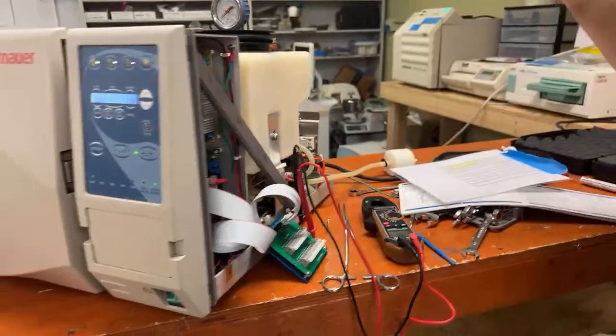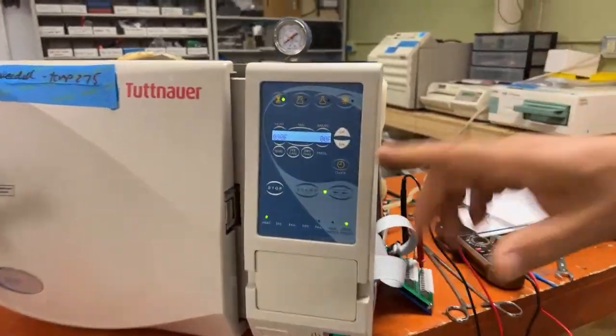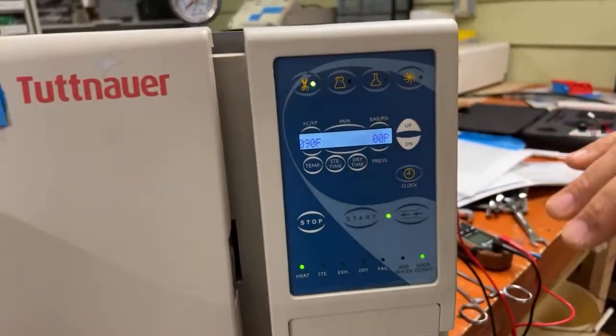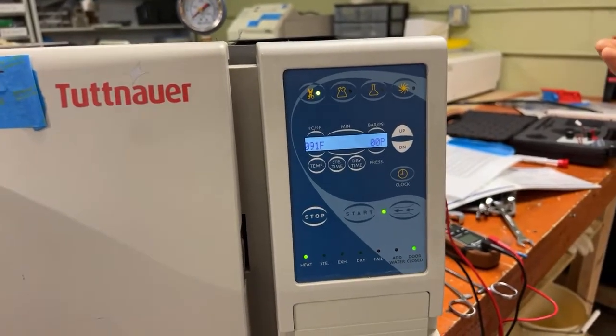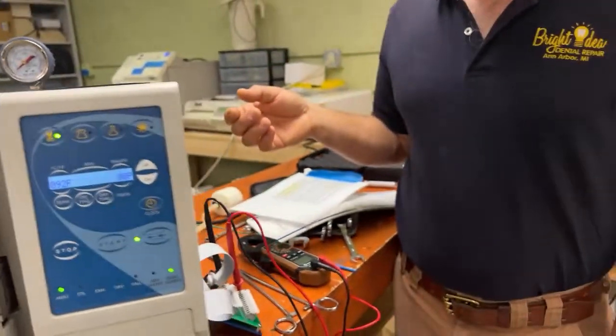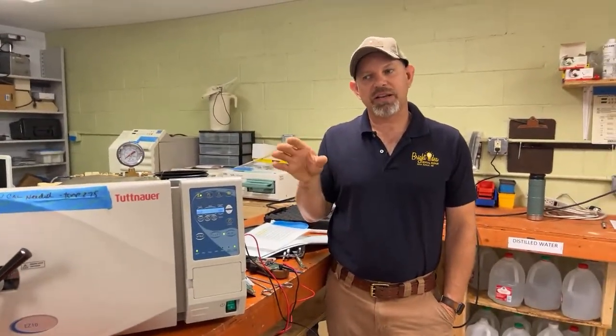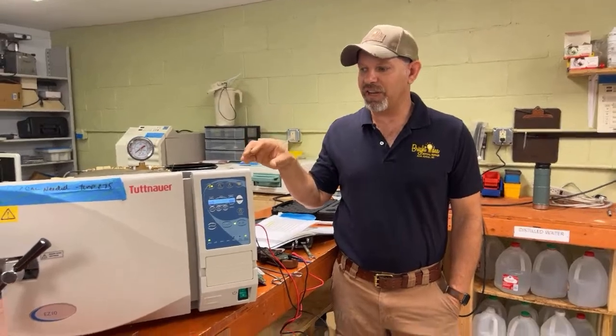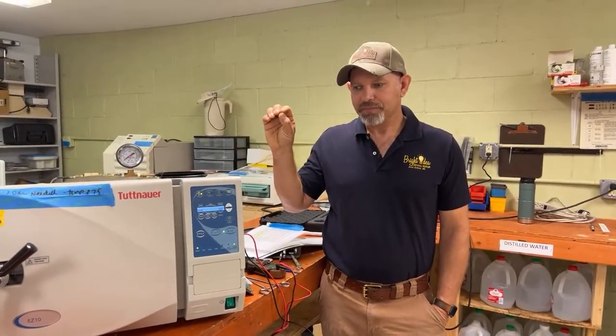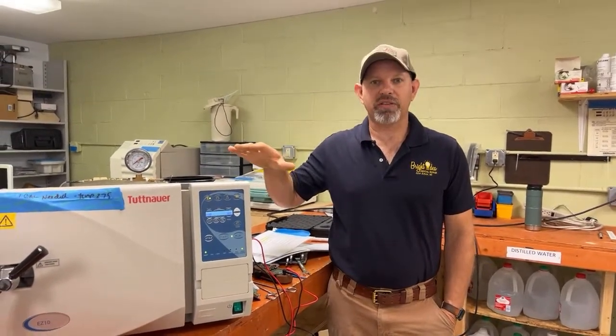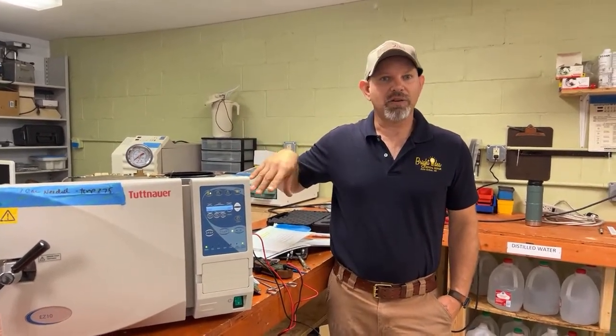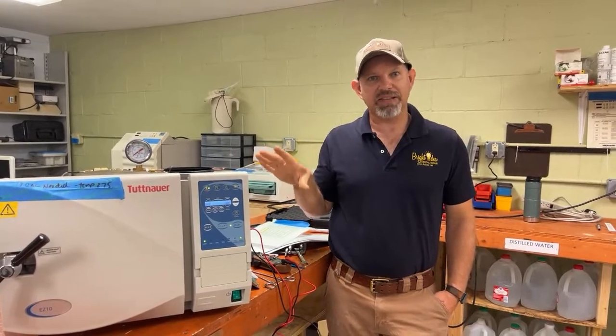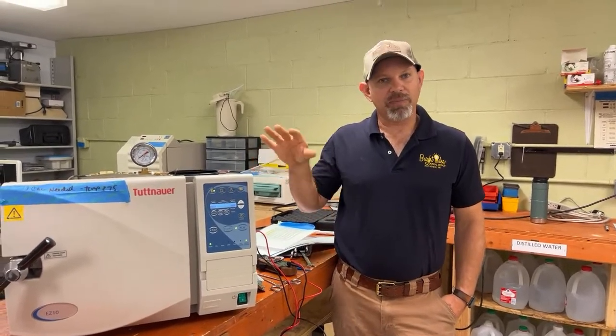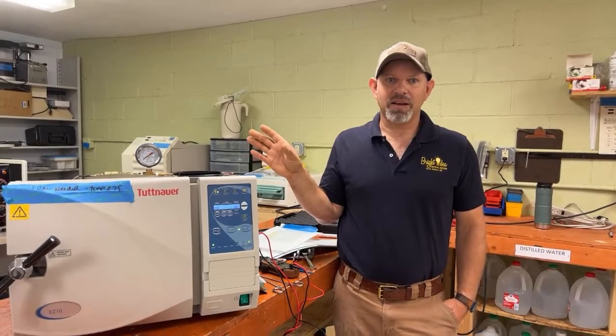Now, let's see. It looks here like I can hear it heating. We're at 90 degrees, so our temperature's going up, as I'm talking about other things relevant to autoclaves with regard to sterilization. It's important that you run a full drying cycle of about 30 minutes on this style of autoclave in order to make sure all your packs are completely dry.